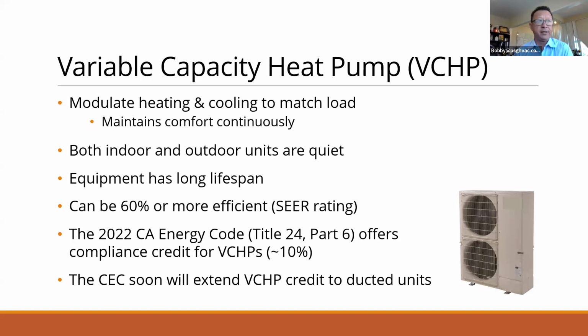Traditional heat pumps used to be 100% on, meet set point, go 6 degrees over or under, and then come back on again. And then you see your compressor contactor pull in, your lights might dim. So there are a lot of benefits to having it variable capacity. The SEER, EER, SEER2 is much higher. Both indoor units and outdoor units are extremely quiet. We have applications in very stringent areas like Newport Beach and Beverly Hills, where the dB rating needs to be around 55. Typically, a lot of these side flow or suitcase style condensing units, where it's very narrow and can be mounted very close to the wall, are extremely quiet. Back to the no compressor contactor, so it's a very soft start for the compressor. So all the equipment has a very long lifespan. Again, there's no compressor contactor pulling in, and it can be up to 60% more efficient.